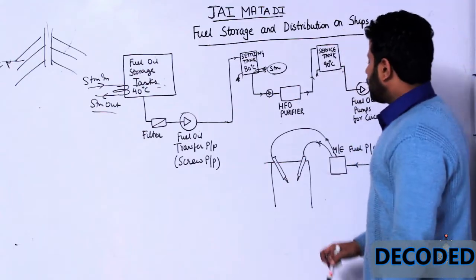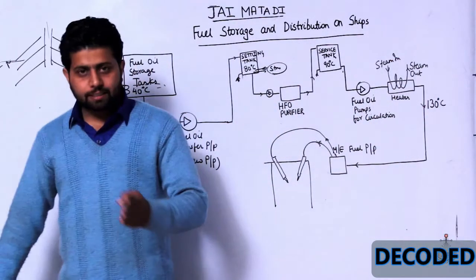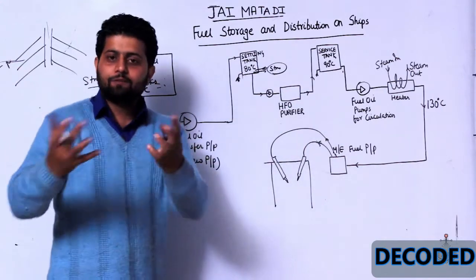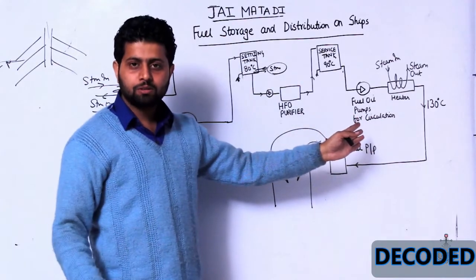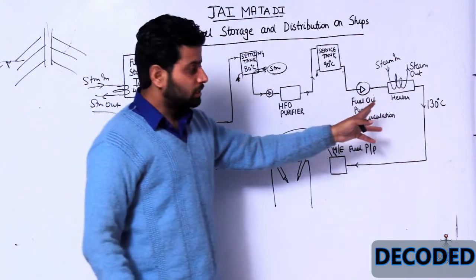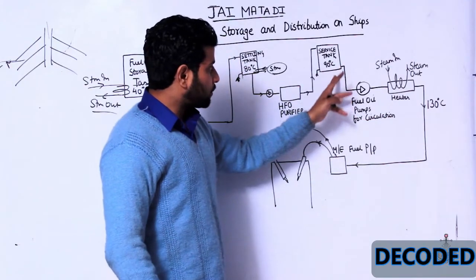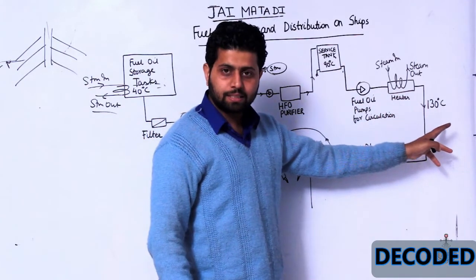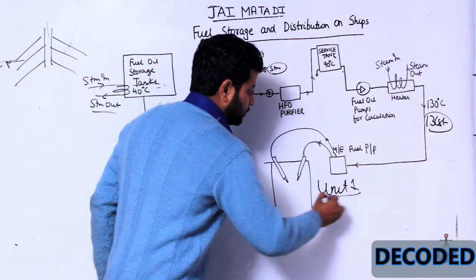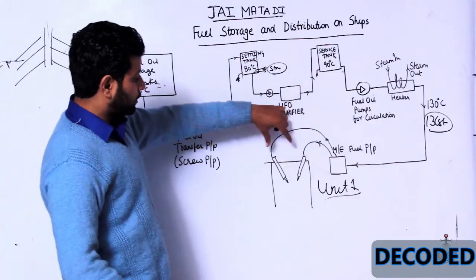In the service tank, the oil is further heated and temperature is increased up to 90 degrees centigrade. The service tank is ready for giving service to the engine. From here, fuel oil booster circulating pumps increase the pressure up to 7 bars and send the oil to a heater where the temperature is increased from 90 degrees centigrade up to 130 degrees centigrade, so that we have 13 cSt viscosity when it reaches the main engine fuel oil pump.